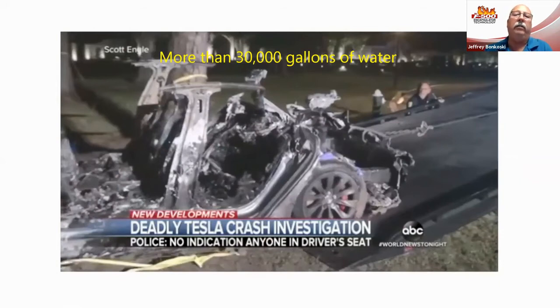And when we start listening to other reports, the actual extinguishment from the fire is being reported to be like 24 minutes, but the rest of the time it's trying to cool the batteries, because when they would stop flowing water, it would reignite. So after that 30,000 gallons, they pretty much just gave up and let it burn. So the question now becomes - this is in a parking structure.